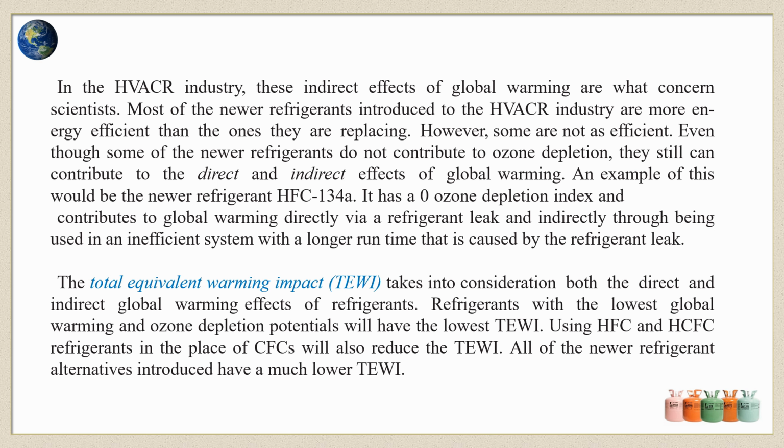The total equivalent warming impact, TEWI, takes into consideration both the direct and indirect global warming effects of refrigerants. Refrigerants with the lowest global warming and ozone depletion potentials will have the lowest TEWI. Using HFC and HCFC refrigerants in the place of CFCs will also reduce the TEWI. All of the newer refrigerant alternatives introduced have a much lower TEWI.